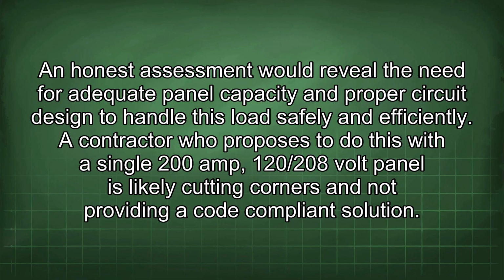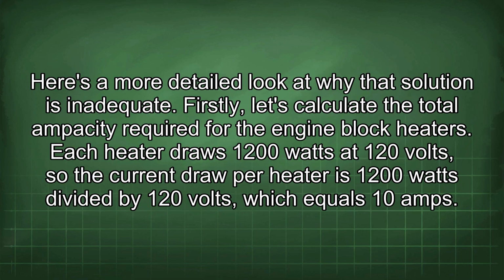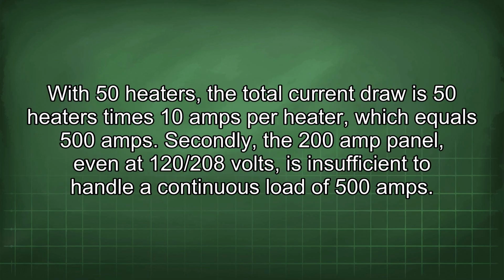A contractor who proposes to do this with a single 200 amp, 120/208 volt panel is likely cutting corners and not providing a code-compliant solution. Here's a more detailed look at why that solution is inadequate. Firstly, let's calculate the total ampacity required for the engine block heaters. Each heater draws 1200 watts at 120 volts, so the current draw per heater is 1200 watts divided by 120 volts, which equals 10 amps. With 50 heaters, the total current draw is 50 heaters times 10 amps per heater, which equals 500 amps.